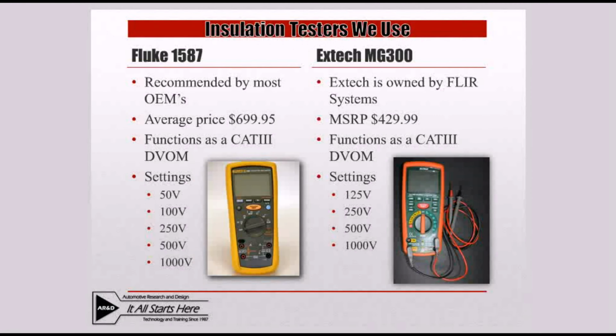The two insulation testers we use regularly are the Fluke 1587 and the Extech MG300. The Fluke 1587 is probably the product line you're more familiar with, and it's currently recommended by most automotive manufacturers. It costs around $700 and serves as a full functional Category 3 digital volt ohm meter as well as an insulation tester with a range from 50 volts up to 1000 volts, covering all vehicles currently produced in the light duty market. It also has a remote actuation button on the test lead for the insulation test, letting you actuate the test from the lead rather than going back to the unit itself.